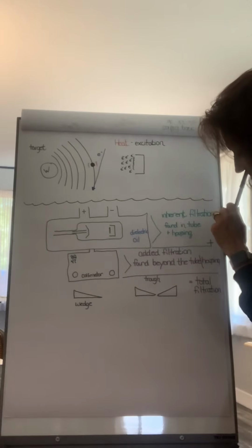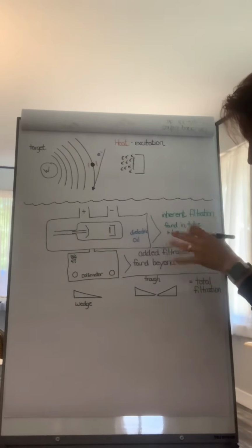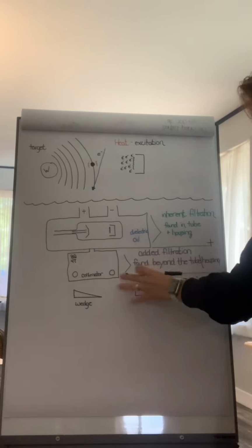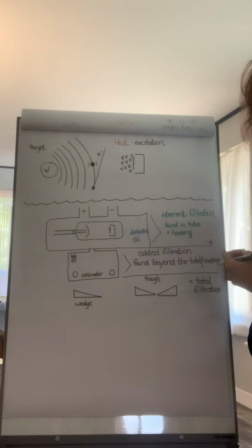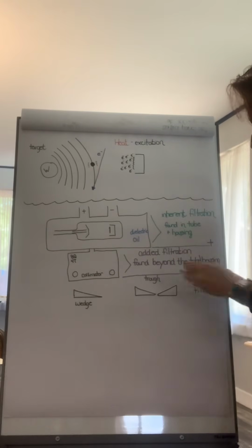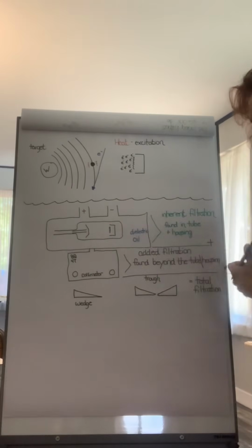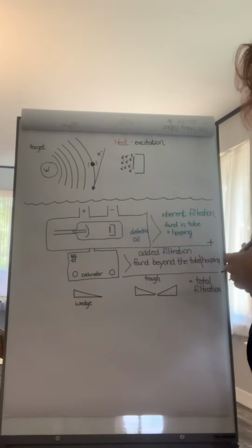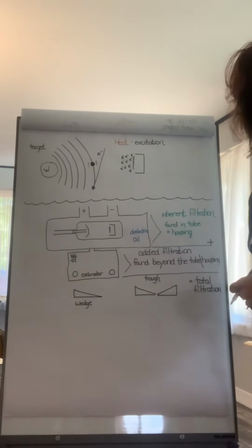There's a light bulb in there. There's some different metals in there. There's lead in the shutters, tin on the back, silver on the back of the mirror. Different things that are in the collimator that also can absorb that low energy radiation. All of this has the potential to stop that low energy radiation that would never make it out to do anything with our image. It would only add dose to the patient.